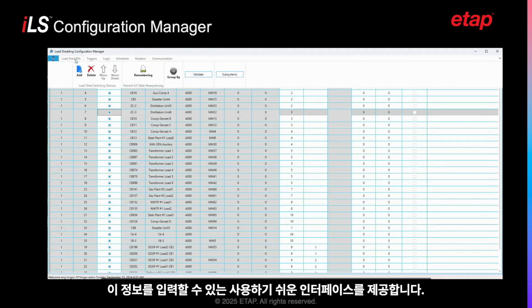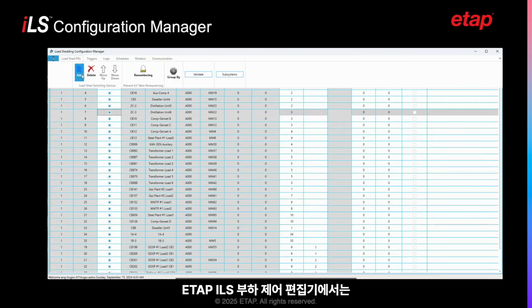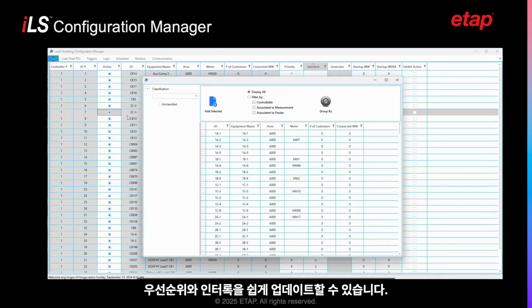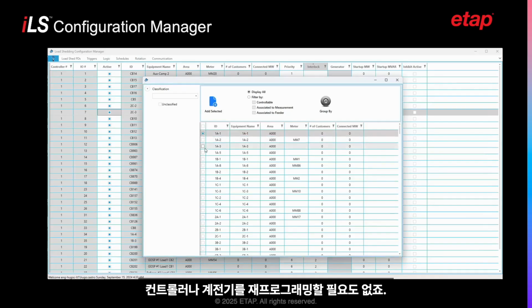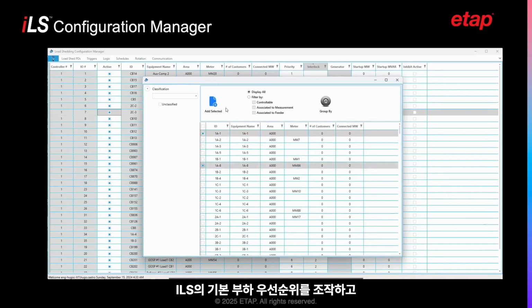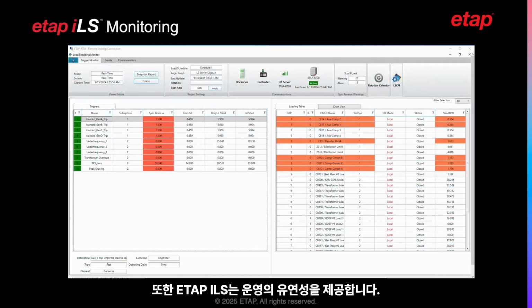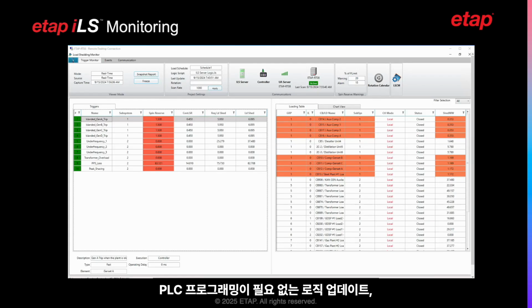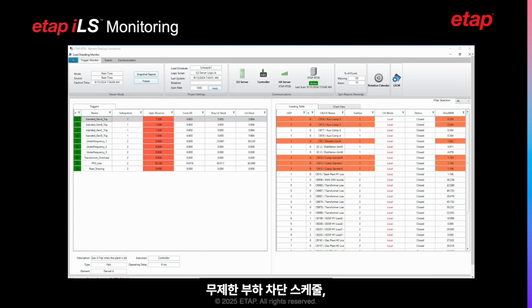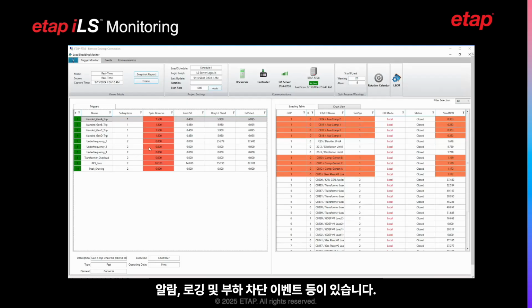ETAP ILS provides an easy-to-use user interface to input this information. In the ETAP ILS load control editor, we can add or remove loads and update priorities and interlocks easily without the need to reprogram controllers or relays. By simply manipulating the ILS default load priorities and grouping loads under the interlock, you can achieve this goal. ETAP ILS also provides flexibility of operation with these features: a friendly user interface, monitoring of spinning reserve and system frequency, update logic without PLC programming, unlimited load shedding schedules, alarm and logging of load shedding events.